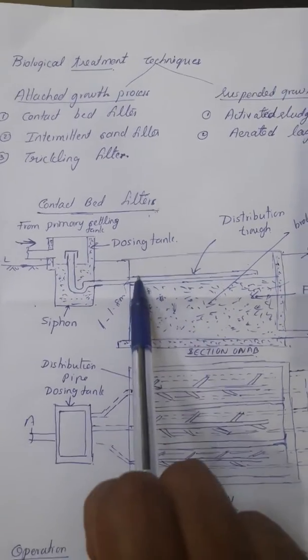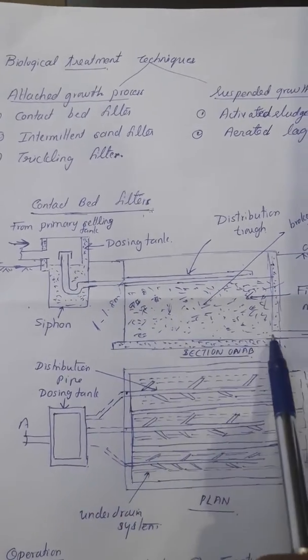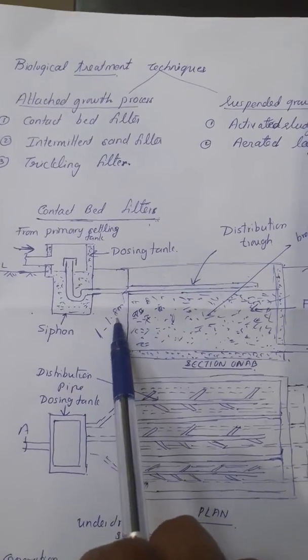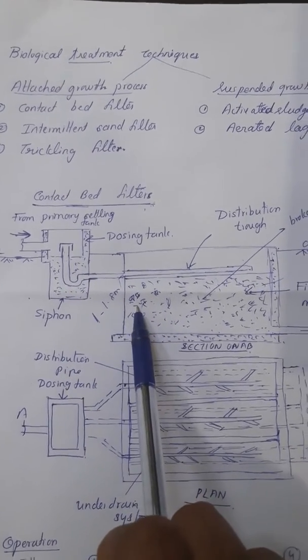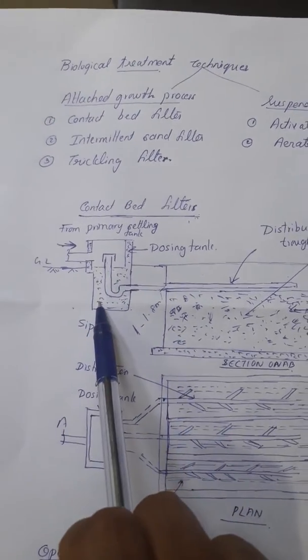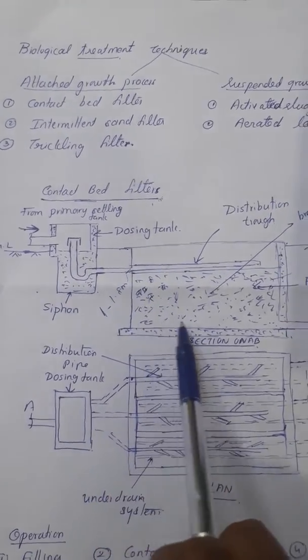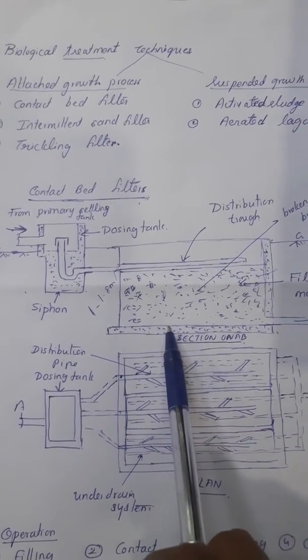The contact bed is a watertight tank of masonry walls and is rectangular in shape. The depth of this filter media varies from 1 to 1.8 meters, and normally we can adopt a depth of 1.2 meters. This tank is generally dug below ground level and lined with watertight cement plaster or concrete surface instead of masonry.